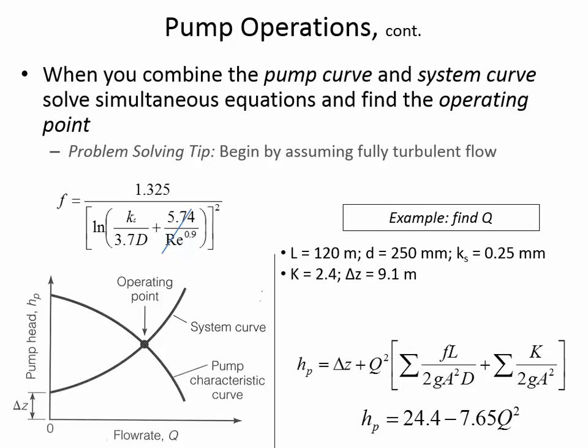H sub P is 9.1, that's the delta Z that's described, plus Q squared times the friction term. We've got an F value of 0.0196, a pipe length of 120 meters, 2G, so 2 times 9.81 meters per second squared. Now we need to put in the pipe's area. The pipe diameter is 250 millimeters. Area is pi d squared divided by 4. The pipe area is 0.04909 square meters. So that's where this 0.04909 meters squared comes from. And we need to square that, as it says in the equation, multiplied by d, 0.25 meters.